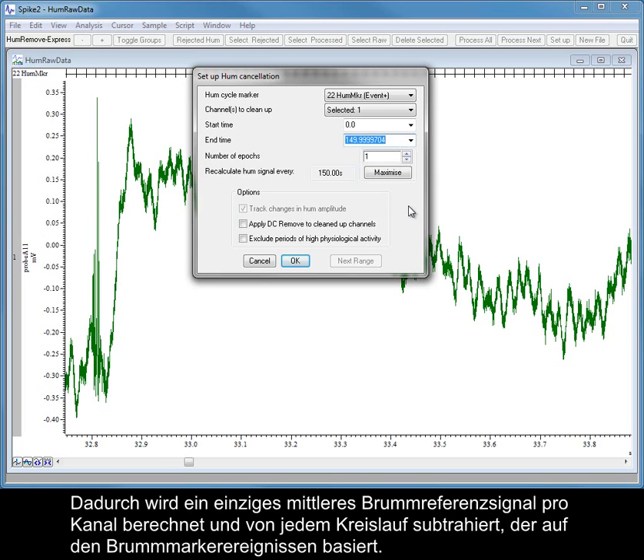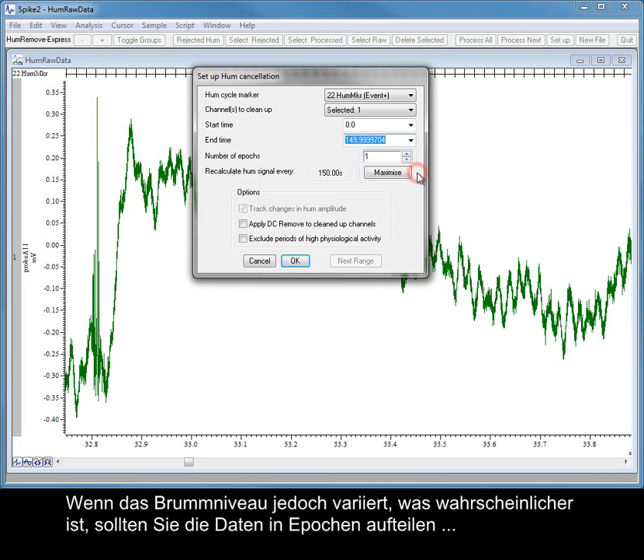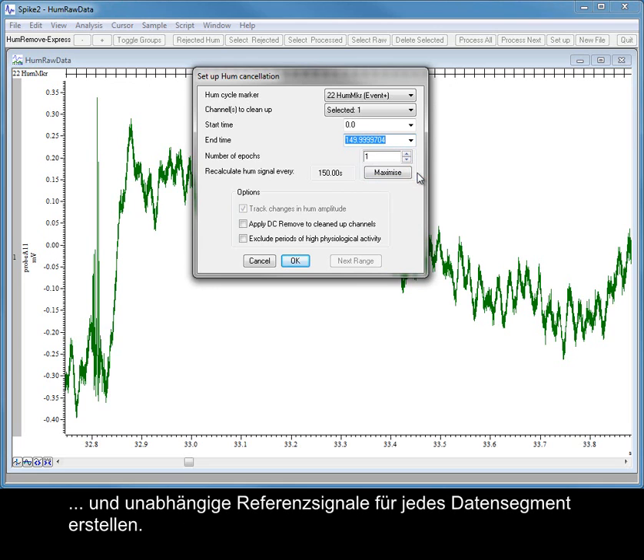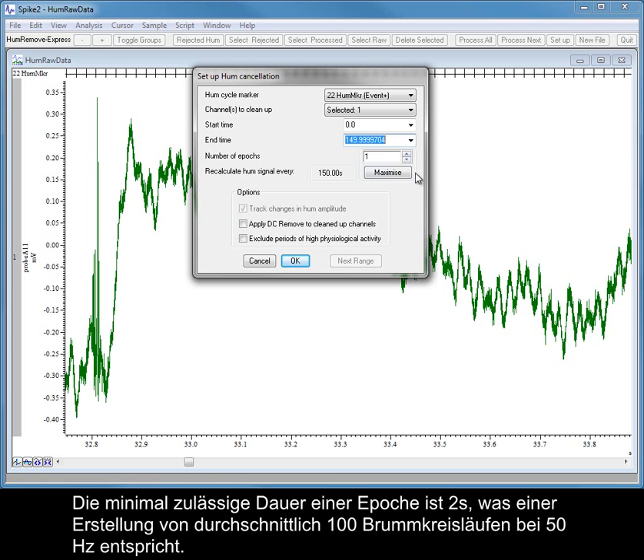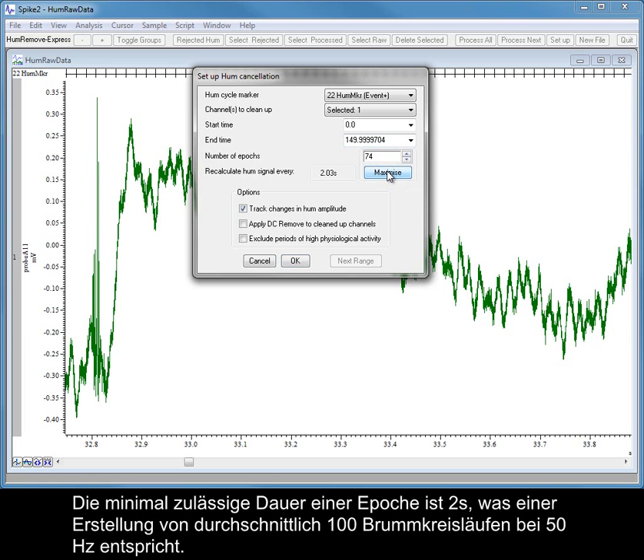This will calculate a single mean hum reference signal per channel and subtract it from every cycle based on the hum marker events. However, if the hum level varies, as is far more likely, you should divide the data into Epochs and generate independent reference signals for each segment of data. The minimum allowed duration for an Epoch is 2 seconds, which will generate an average of 100 hum cycles at 50 Hz.